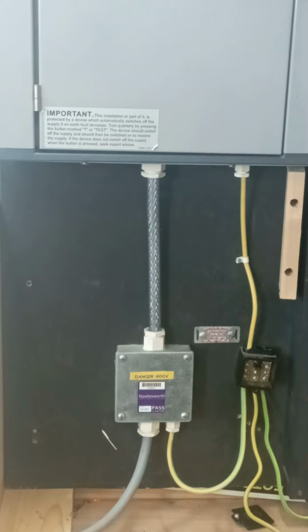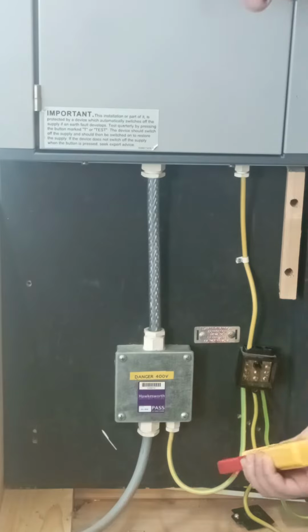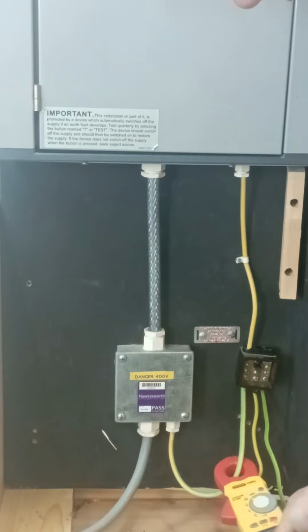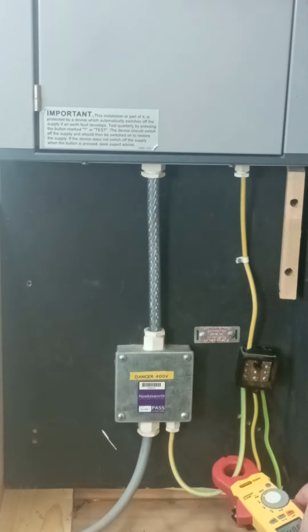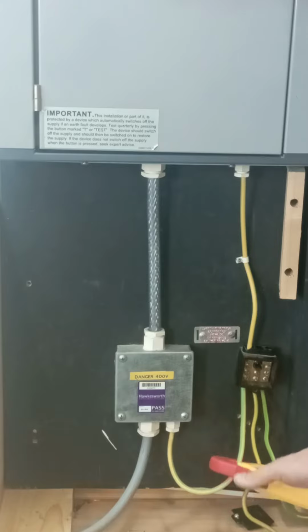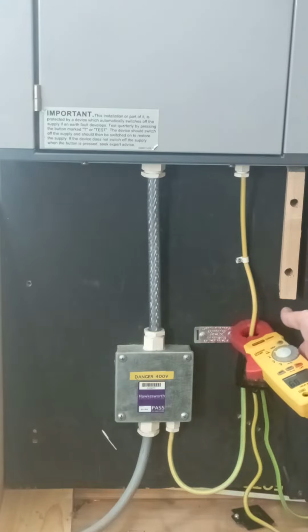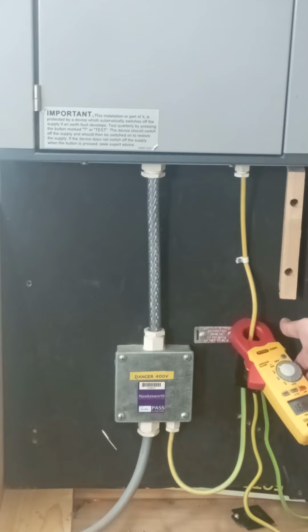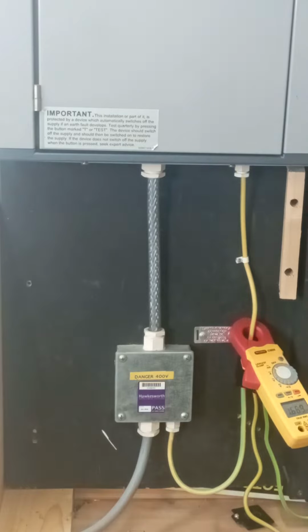The reason for that, folks, is these are just two pipes sitting on the board. Obviously, if they were introducing a local earth potential, there would be current flowing through them as well. Okay, and then when I check my earthing conductor, you'll see there I've got that same value that we had on the protective conductor. So we then go down through our controlled shutdown. You'll see there I've turned off, or I'm starting to turn off, some circuit breakers up on the top board, and any second now we should see that current drop away.